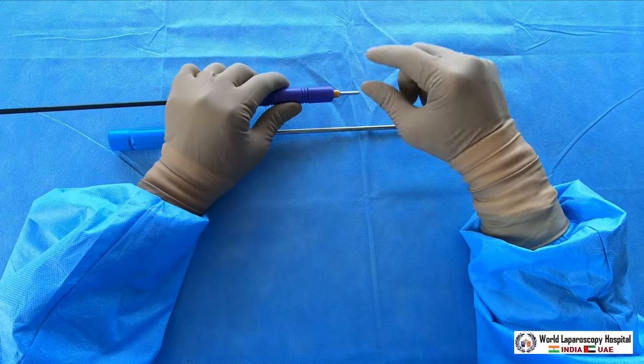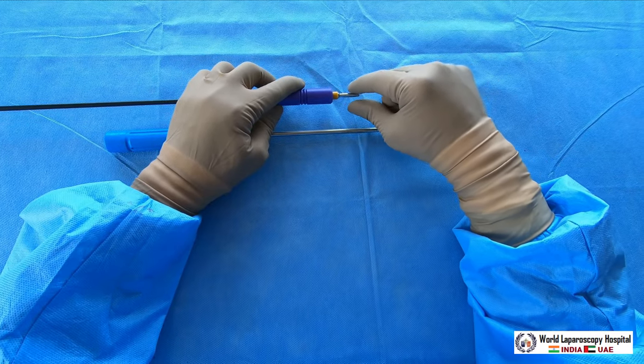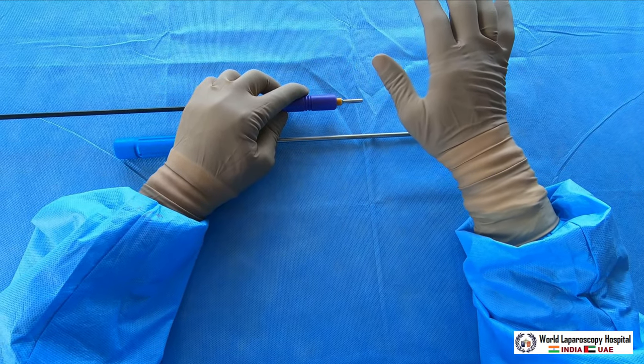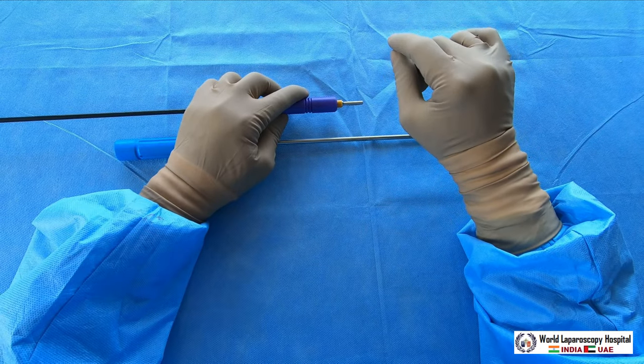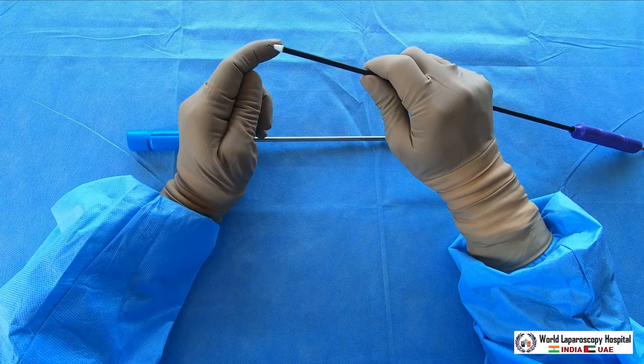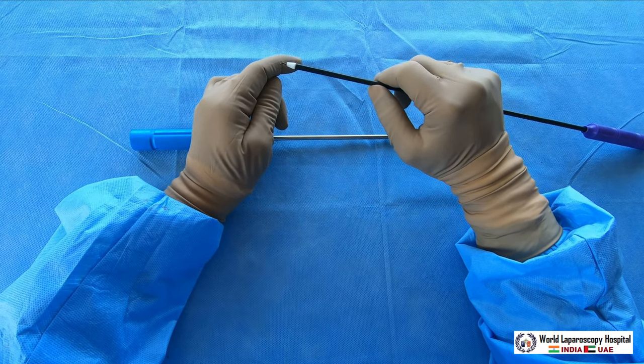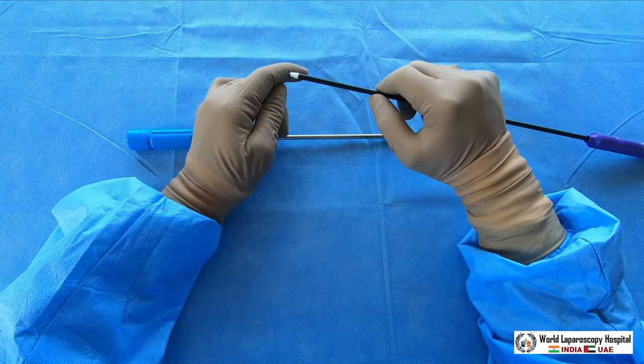There is a very useful job of the hook: you should use cutting current. You have to attach monopolar and always use the hook with the yellow pedal. Sometimes the heel of the hook — that is called the heel of the hook — can be used for coagulation current, which you can use for fulguration.